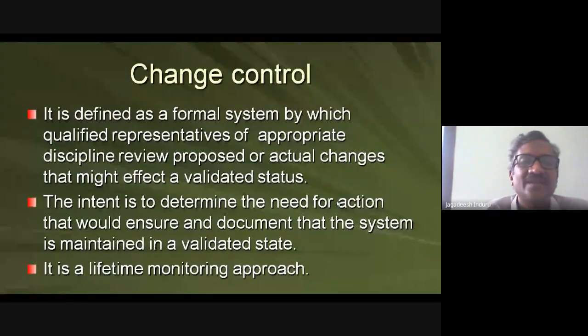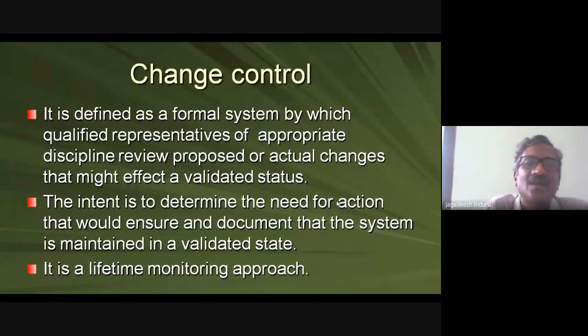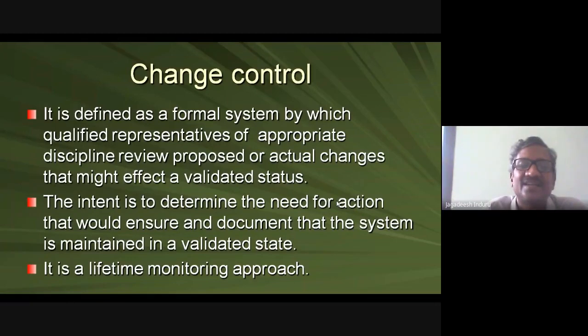Change control is defined as a formal system by which qualified representatives of appropriate disciplines review proposed and actual changes that might affect the validation status. The intent is to determine what actions are needed to ensure the system remains in its validated state — for example, a tray dryer qualified for up to 200°C cannot be used at 250°C, and the SOP reflects this.